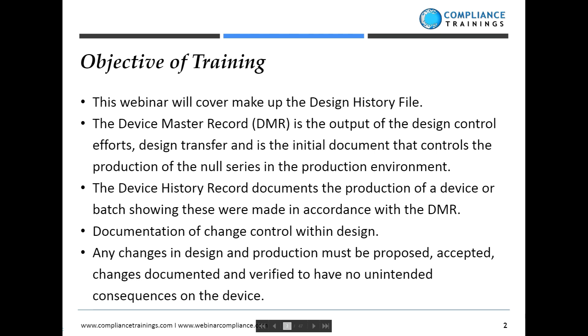The webinar covers the makeup of the Design History File. The Device Master Record is the output of the design control efforts, design transfer, and the initial control documents that control production. The Device History Record documents the production of a device or batch, showing it was made in accordance with the Device Master Record. Documentation of change controls within design is also covered — any changes in design and production must be proposed, accepted, documented, and verified to have no unintended consequences on the device before they're put into place.